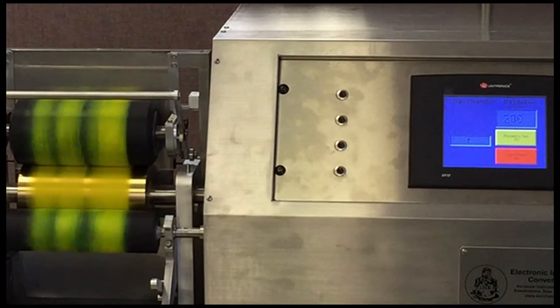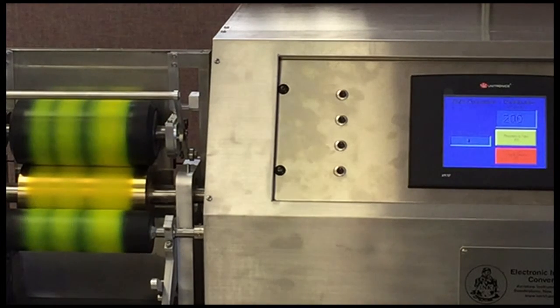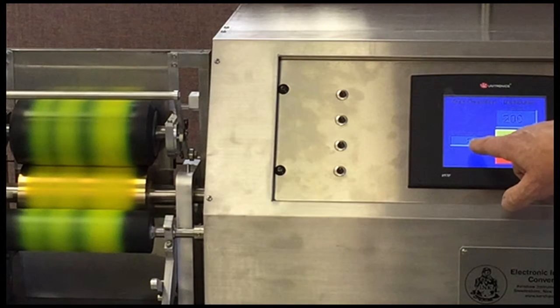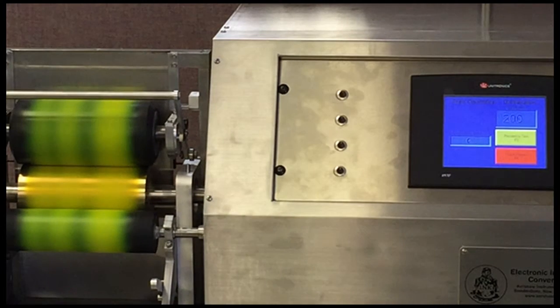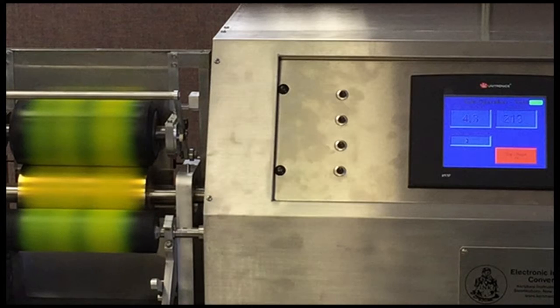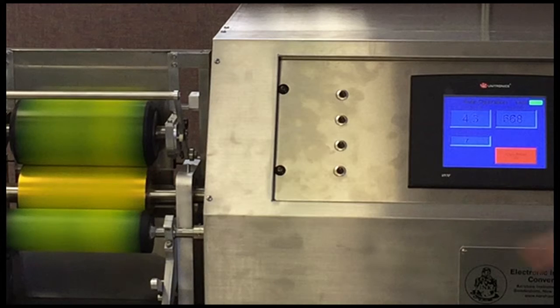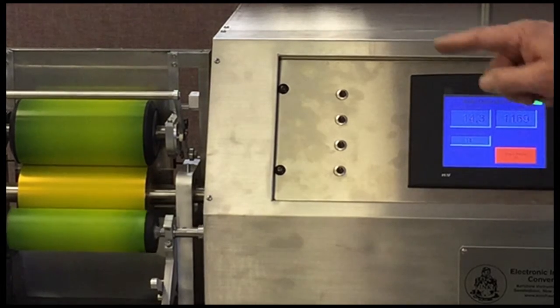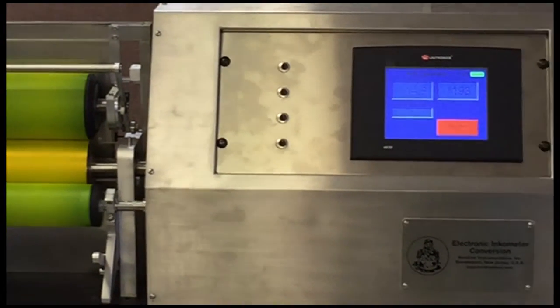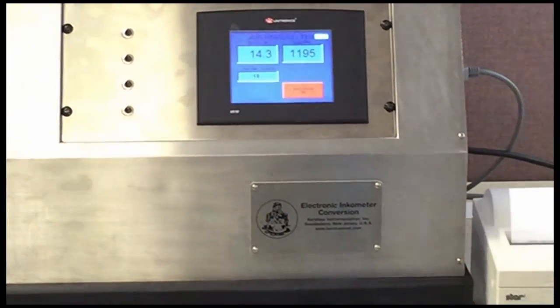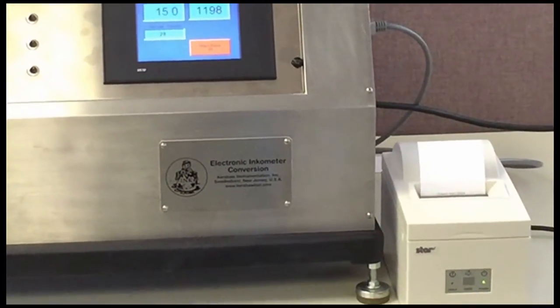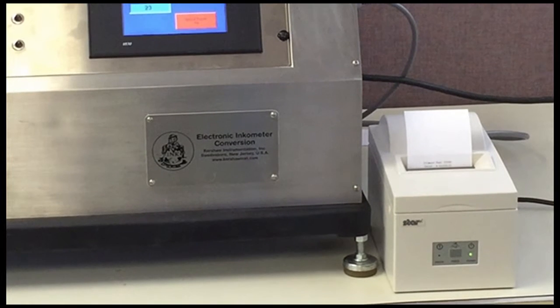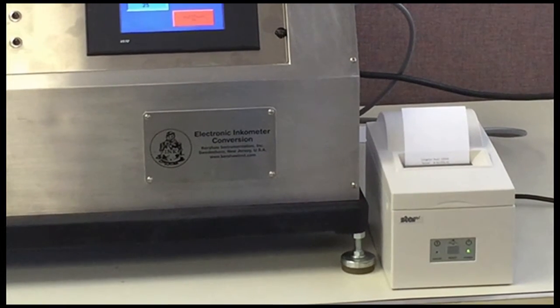Now what's happening is it's running at 200 RPM to distribute the ink, and our distribution is counting down. All right, now we've started our test. It's going up to 1200. You can see the ink is distributed, and our printer has printed out the header. Now every 10 seconds, it will take a tack reading and print out the results on the printer. So we're going to let this run for a little bit.